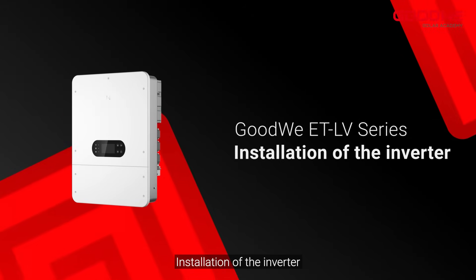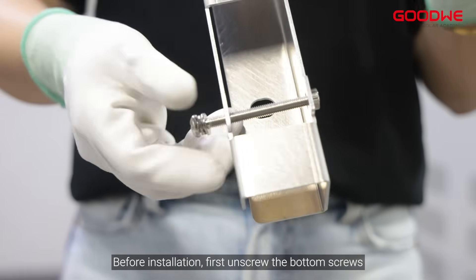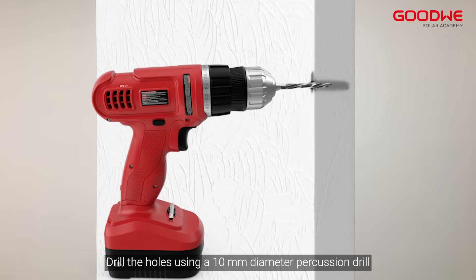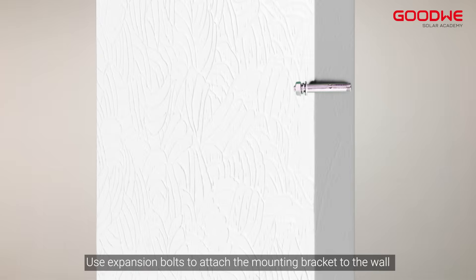Installation of the inverter. First, take out the mounting plate. Before installation, unscrew the bottom screws. Drill the holes using a 10mm diameter percussion drill, ensuring a depth of approximately 80mm. Use expansion bolts to attach the mounting bracket to the wall.